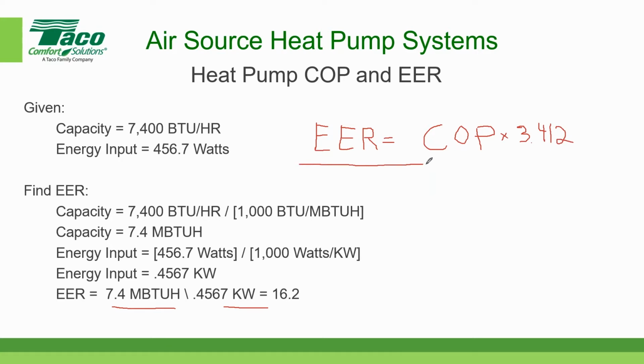So one of the things about EER, if you're trying to compare the COP of one machine versus another, but one happens to be in EER and the other one happens to be in COP, the EER is equal to the COP times 3.412. And the opposite is true. So let's do it this way.